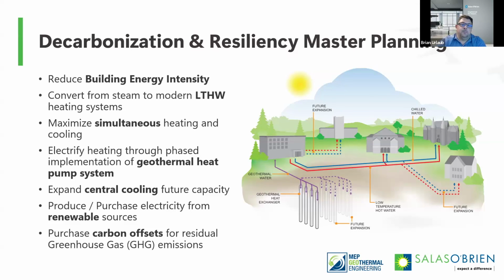Residentially, the air source heat pump technology has gotten much better. They have these cold climate heat pumps now that'll run down to about 0, even below 0. Now the efficiencies aren't great, obviously, when you get down to that cold, because you can't really change physics. The refrigerants, the components, the compressors are no different from a geothermal heat pump to an air source heat pump. So the energy source is the air versus the ground.